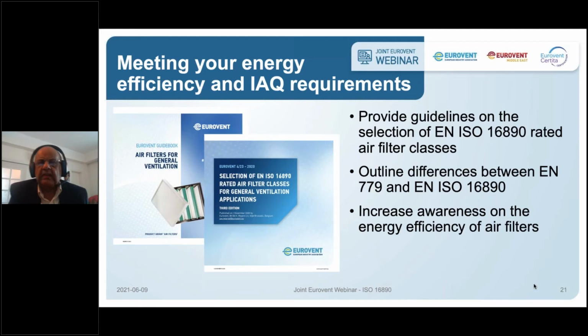Basically, what's happening is that Eurovent certification has been able to grade filters depending on the kilowatt-hour a filter consumes working for one complete year. The gradation goes from a value of say 700 or 800 kilowatt-hours for the best possible filter that manufacturers have designed, to almost double that value for a lower energy class filter.